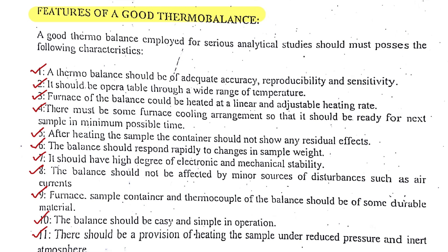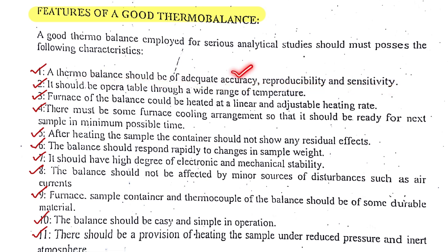The qualities of a good thermobalance are summarized here. A thermobalance should be of adequate accuracy, reproducibility, and sensitivity. Accuracy means how close your value is towards the actual value. Reproducibility means that if we repeat a certain experiment, it should give the same answer again and again. Sensitivity means how much a change in the environment is detected by your instrument.